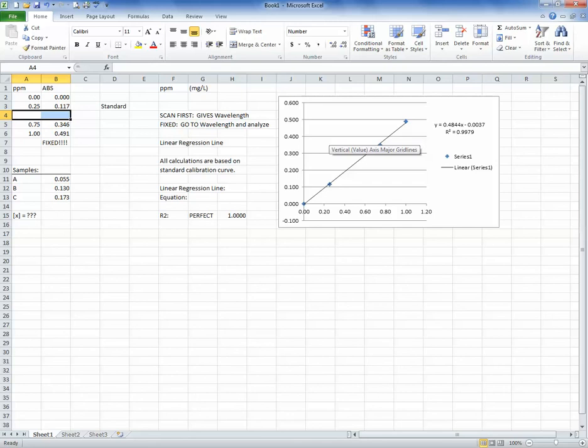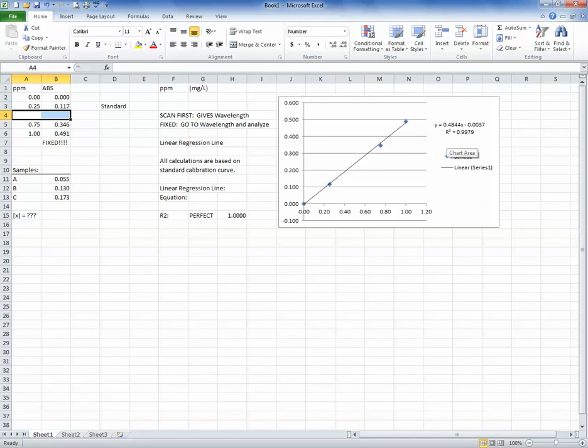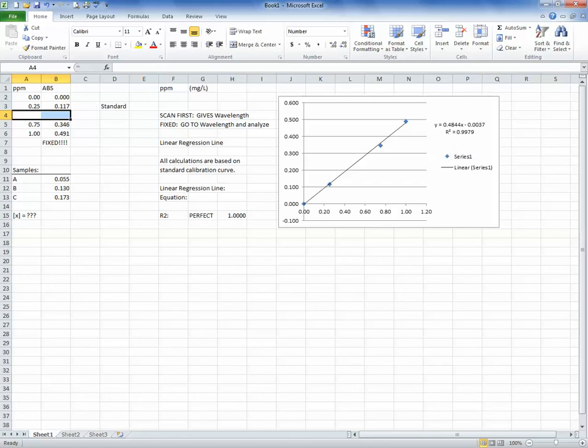So that's my calibration curve, and we use this calibration curve to determine what my sample concentrations are going to be. And you know, this makes me feel pretty comfortable. Visually, it looks like a straight line. My r squared value is 0.998, basically, if I rounded that up. That's really close to a one. I know I'm not going to get perfect. Maybe if you're lucky, you do, or if you're really, really good at what you do, you'll get a one. But this is acceptable. I feel good about these numbers. So in the next video, we'll talk about how to use this calibration curve now, and how to use the equation and solve for our samples. So again, our samples are A, B, and C, and I've got absorbances that go with each one of those, and we need to figure out what these concentrations should be. So that's what we'll talk about next.